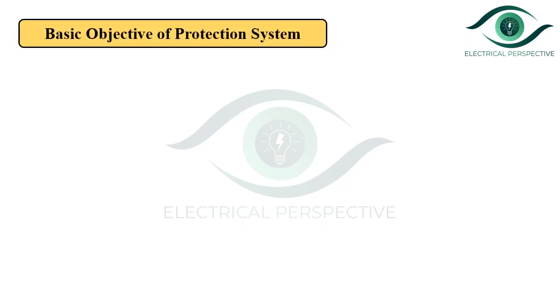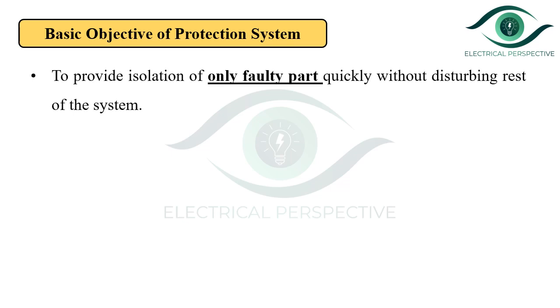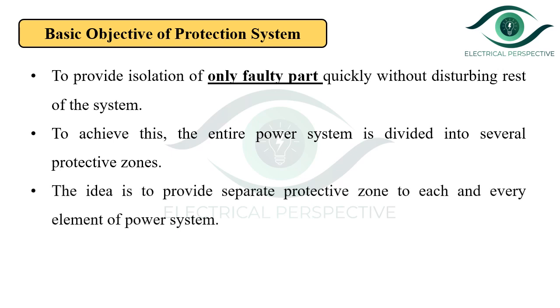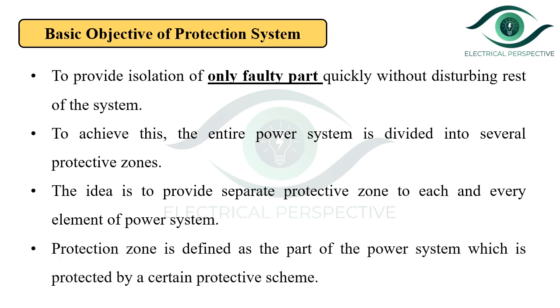What is the basic objective of a protection system? The basic objective is to provide the isolation of only the faulty part quickly, without disturbing the rest of the system. To achieve this objective, the entire power system is divided into several protective zones. The idea is to provide a separate protective zone to each and every element of the power system. A protection zone is defined as the part of the power system which is protected by a certain protective scheme.